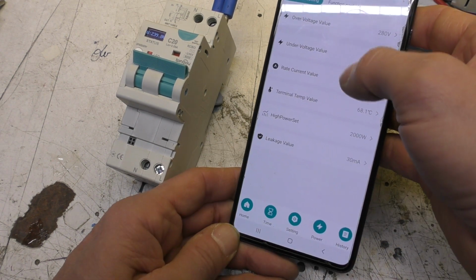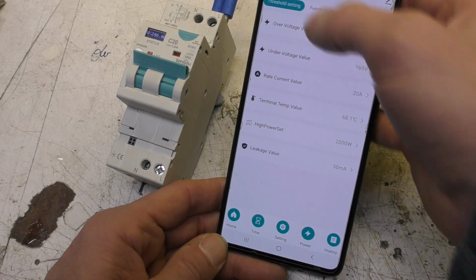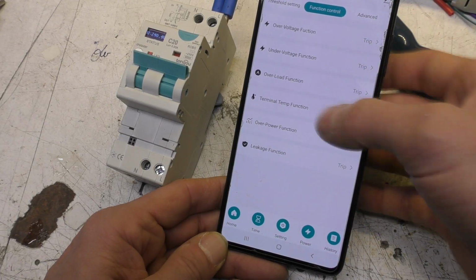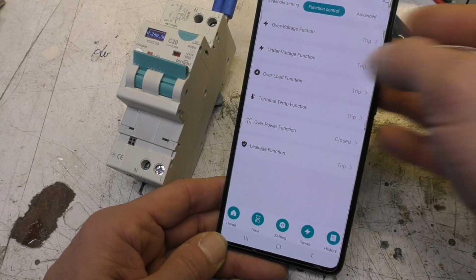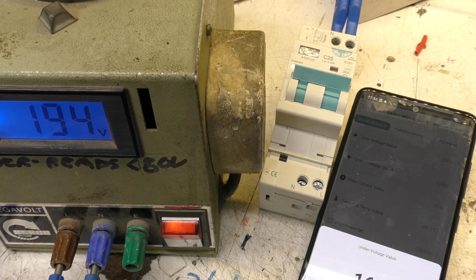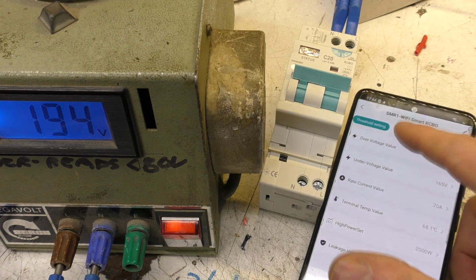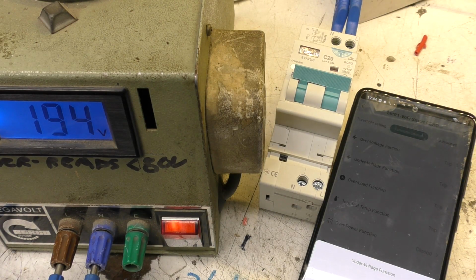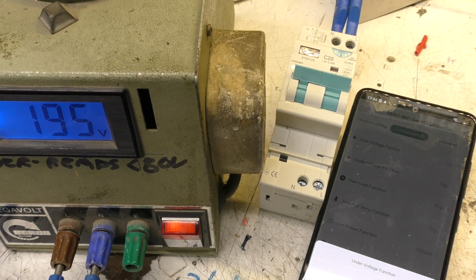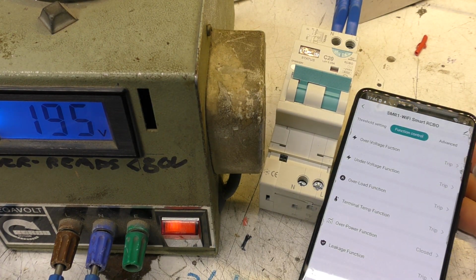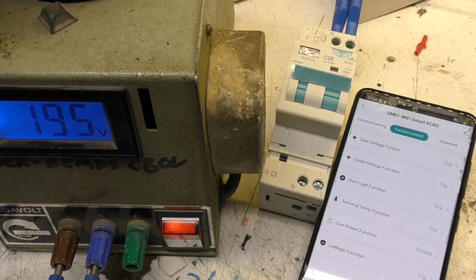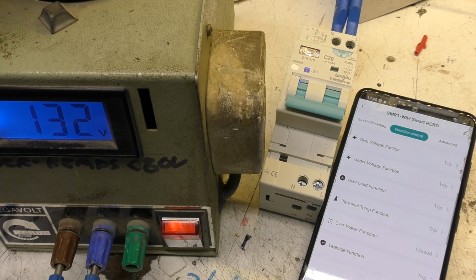Because we've got over and under voltage trips, and for most of these functions you can tell it what to do in these situations. So for example, turn off if the voltage goes below 165. And for most of these settings, you've got three options: you can tell it to trip, send a notification, or do nothing. So for example, we set an under voltage trip, and we reduce our supply voltage. After a few seconds, it trips, which is a nice function.